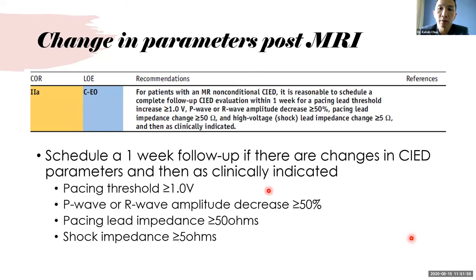There are also guidelines for monitoring of devices if there are significant changes in parameters post-MRI. These guidelines recommend monitoring parameters such as a pacing threshold change of more than 1 volt, the sensing P wave or R wave decreased by more than 50% from baseline, a pacing impedance change of more than 50 ohms, or a shock impedance change of more than 5 ohms. Of course, there may sometimes be measurement changes, but these are the parameters given by the guidelines.